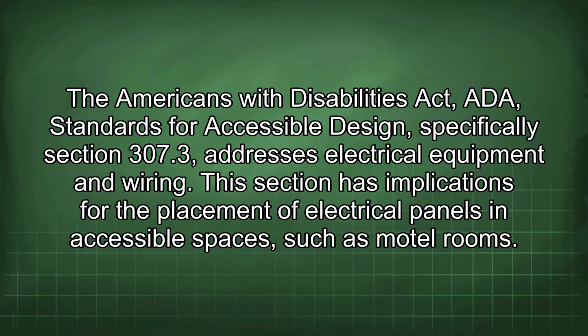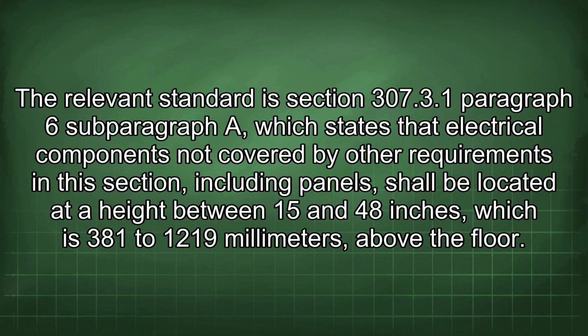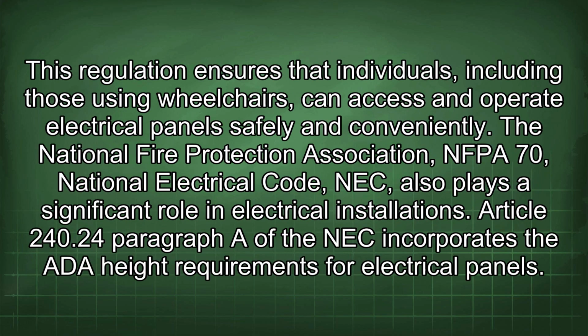The Americans with Disabilities Act, ADA, Standards for Accessible Design, specifically Section 307.3, addresses electrical equipment and wiring. This section has implications for the placement of electrical panels in accessible spaces, such as motel rooms. The relevant standard is Section 307.3.1 paragraph 6 subparagraph A, which states that electrical components not covered by other requirements in this section, including panels, shall be located at a height between 15 and 48 inches, which is 381 to 1219 millimeters above the floor. This regulation ensures that individuals, including those using wheelchairs, can access and operate electrical panels safely and conveniently.